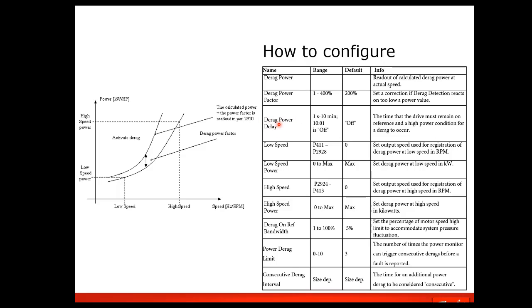And then there is a delay between crossing this threshold, so we don't want to just go into derag at any little blip of power. There is a delay between being over this line and then triggering to go into derag. And in the configuration here, this line is developed based on 2 points, a low speed and a high speed. Generally, the high speed is the full speed of the pump, and the low speed is set to a minimum running speed where we're actually developing power. So we don't want to set this at 0, but typically we set this at around 60% speed.